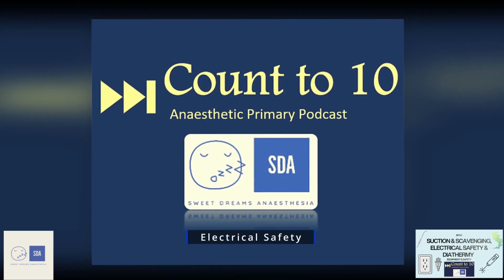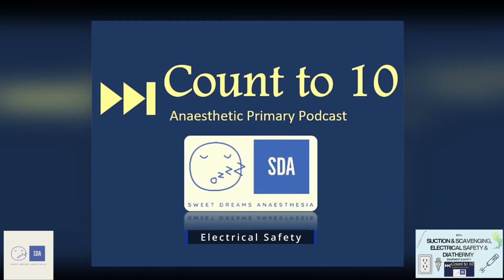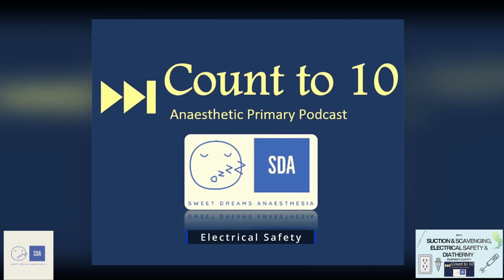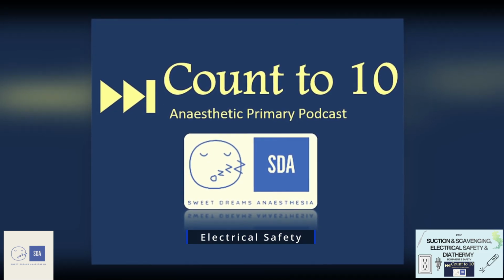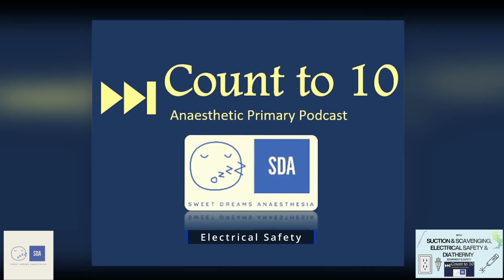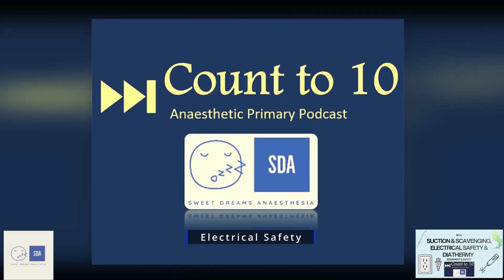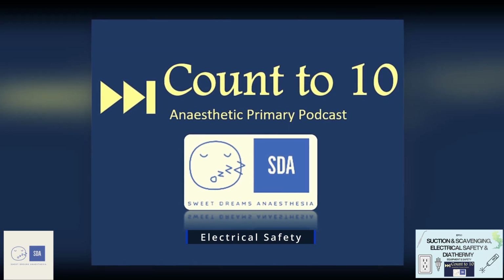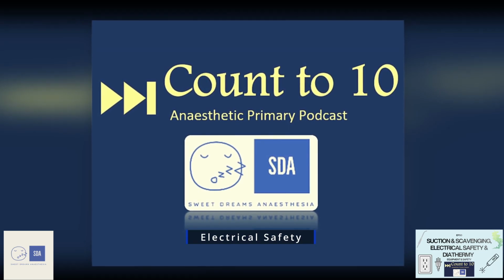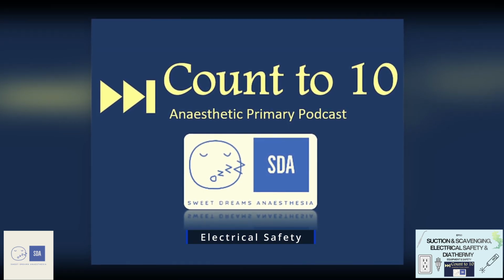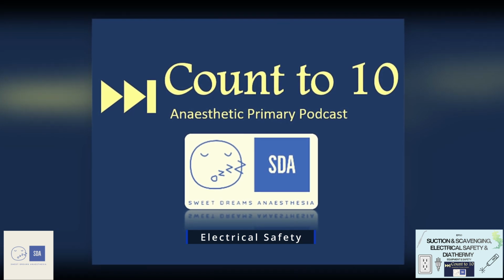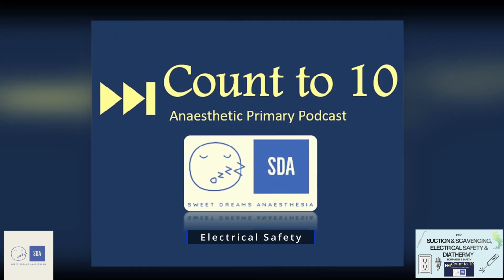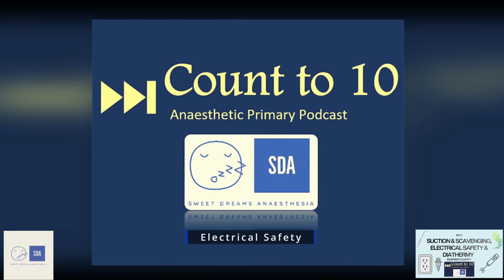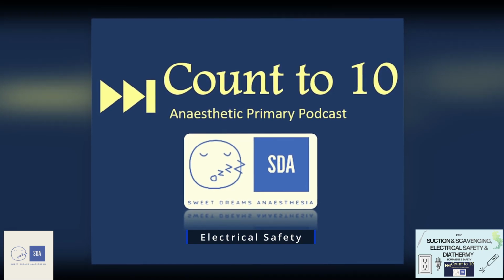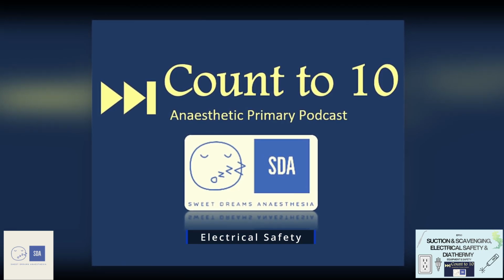Comparatively, a blue power socket is connected to a UPS, which is an uninterruptible power supply. And this provides an even higher level of backup than a backup generator. So if there's a disruption to the main power supply, there'll be 0 disruption if your power socket is connected to a blue power point. This also means you should be cognizant of the fact that you don't put everything into the blue power supply, because it's going to take up a lot of energy from that uninterruptible power supply unit.